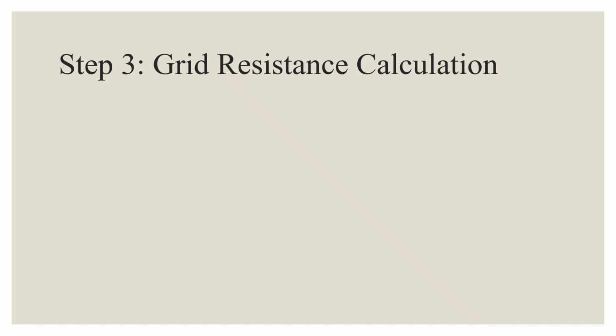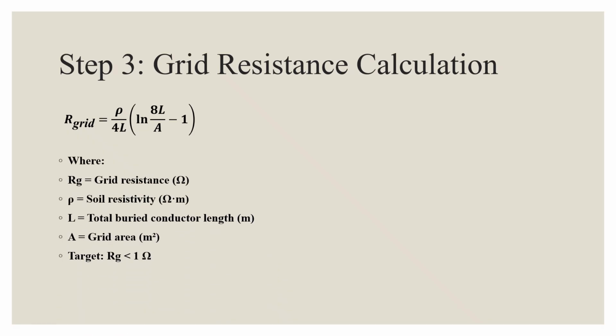So the third step is to calculate the grid resistance. The resistance of the entire grid is calculated using the following formula, where rho is the soil resistivity, A is the grid area, and L is the total conductor length. Our goal is to keep the resistance less than 1 ohm, ideally around 0.5 or lower, to ensure quick dissipation of fault currents.